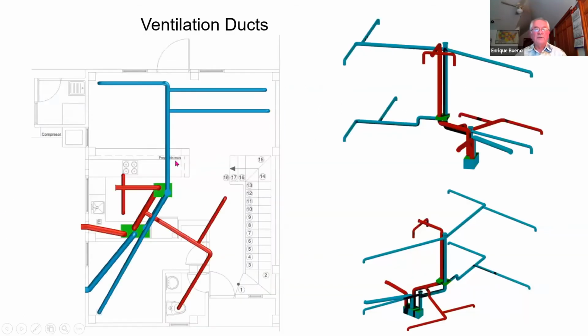This shows the ventilation ducts diagram. The trunks are 20 centimeters or 8 inches. The branches are 15 centimeters diameter, 6 inches, and the 8 inches are specified by Minotair, so we're following their guidelines. And the twigs are 12.7 centimeters, 5 inches diameter. The ducts will be insulated with 4 centimeters, 1.5 inches, of fiberglass pad wrap, to prevent condensation.